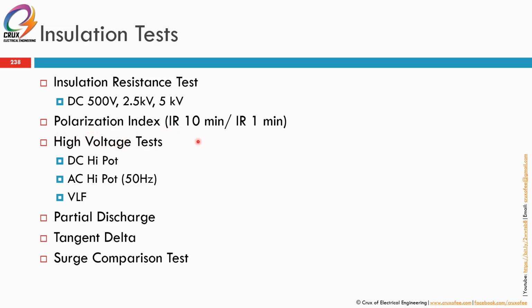Then we will also do the polarization index. Polarization index is mainly for machines, like generators or motors. Some fellows also propose PI for a transformer, but sometimes the PI reading for a transformer may be misleading, because you might not get as high as even 1.5 for a maintenance acceptance. For commissioning, normally we require a minimum PI of 2.0. For maintenance it is around 1.5. So for a transformer it's a little bit misleading, but you can do it just to have a trend for that.